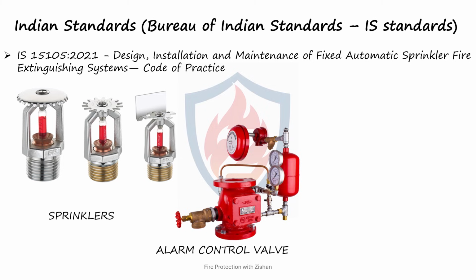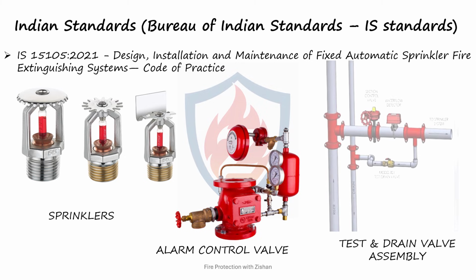On the right is the test and drain valve assembly. This assembly plays a vital role in routine inspection, testing, and maintenance. It is used to verify proper water flow, check alarm operation, and safely drain the system when necessary. Together, these components work in accordance with IS 15105 to ensure reliable fire detection, alarm activation, and fire suppression. Compliance with this standard helps improve life safety, minimize property damage, and maintain the overall effectiveness of the fire protection system.